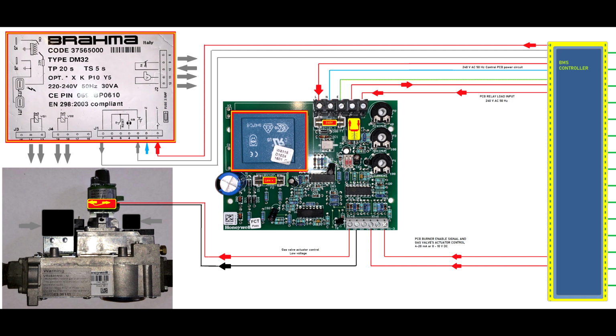For this Brahma controller to start, the connection between number 3 and number 7 of the Brahma controller must be short-circuited, must be closed. As you'll see, there are 2 wires that go back into this building management control, and they are connected to an output, which means it is only a voltage-free relay. This relay will close the circuit and act like a thermostat, and then the Brahma controller will be enabled.